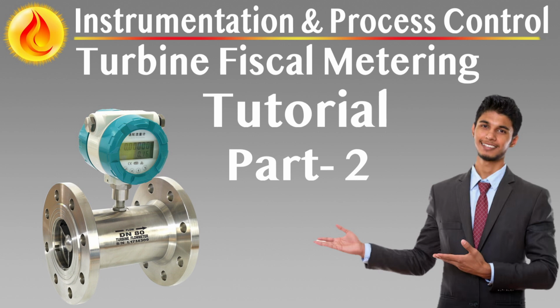Electrical cabling, segregation, and grounding practices. The manufacturer is responsible for all cabling within the metering skid and equipment panel, including proper routing, protection, and termination. Cables leaving the skid to interface with plant-wide systems must be specified by the manufacturer for supply by the site contractor. Signal types, including analog, digital, and power, must be physically segregated to prevent interference and ensure system performance.